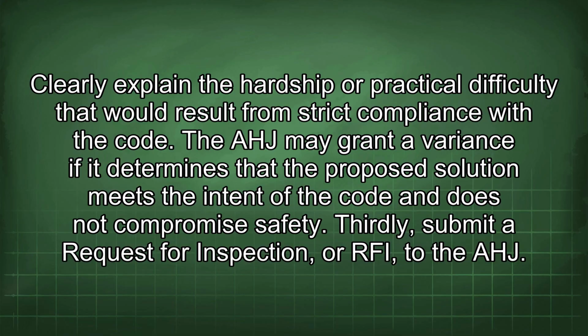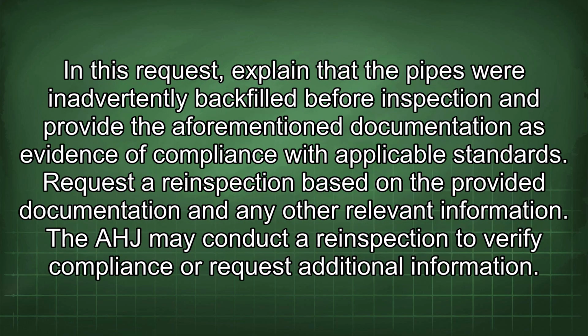Thirdly, submit a request for inspection (RFI) to the AHJ. In this request, explain that the pipes were inadvertently backfilled before inspection, and provide the documentation as evidence of compliance with applicable standards. Request a re-inspection based on the provided documentation and any other relevant information. The AHJ may conduct a re-inspection to verify compliance or request additional information.